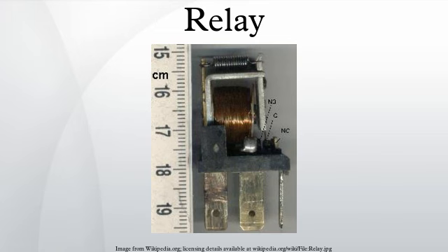Mercury-wetted relay. A mercury-wetted reed relay is a form of reed relay in which the contacts are wetted with mercury. Such relays are used to switch low-voltage signals where the mercury reduces the contact resistance and associated voltage drop, for low-current signals where surface contamination may make for a poor contact, or for high-speed applications where the mercury eliminates contact bounce. Mercury-wetted relays are position-sensitive and must be mounted vertically to work properly. Because of the toxicity and expense of liquid mercury, these relays are now rarely used.